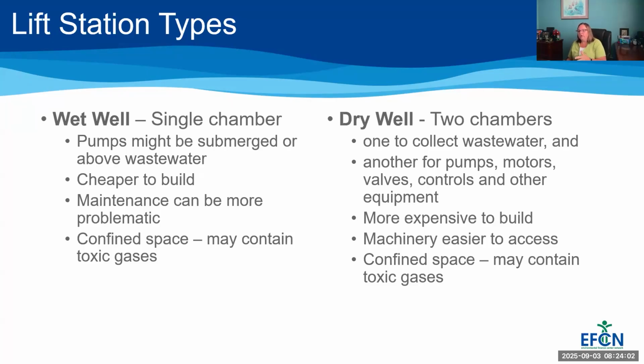With the dry well, your machinery, all of your mechanical equipment is in that dry space, that dry room. So oftentimes the larger lift stations in big cities or areas where you have really high flow rates, maybe industrial type situations, you might have a dry well lift station, because that way you can get to those pumps, you can get to those valves with ease.